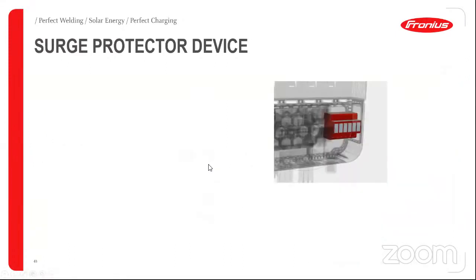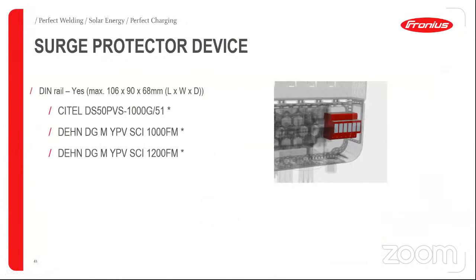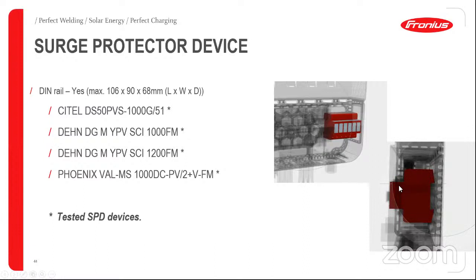The only important thing to remember when we are selecting the SPD is this size. So please keep in mind those numbers so you are not connecting one SPD that is not allowed, because if we do that, we can damage the inverter if it's not closed correctly. So this is the allowed size. These are some of the brands that have these sizes, but if in the market there is another brand, you can also use it. But as I said, please keep in mind the maximum dimensions of the SPD.